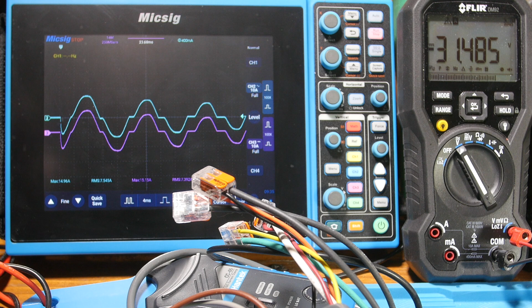Alright, so that was the first one, but our peak was only around 15 amps. I would expect to see a lot higher than that. But see where the switch got turned on, if you look at where the waveform is, it was right after the peak of the negative as it's coming up, so the voltage wasn't at its peak value there, I don't think. It was already around the bottom curving up. Okay, so let's try it again. I'll reset this to max, and we'll have to discharge the output caps.